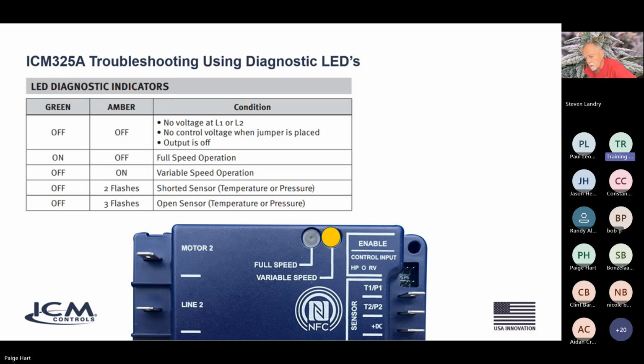Now, if you have the green light on, but the amber light off, it just means you're in full speed operation. If you have the green light off, but the amber light on, it means you're in variable speed operation. And we denote that by the words that are printed right on the controller. Now, if your green light is off, but you get a 2 flash code on the amber light, it means you have a shorted sensor input. And if you have the green light off and you have 3 flashes on the amber LED, that means you have an open sensor. Your sensor's not working. So we can give you some indication of how this thing is working and a little bit of troubleshooting feedback for the technicians.